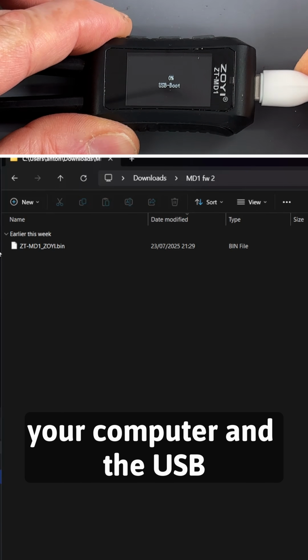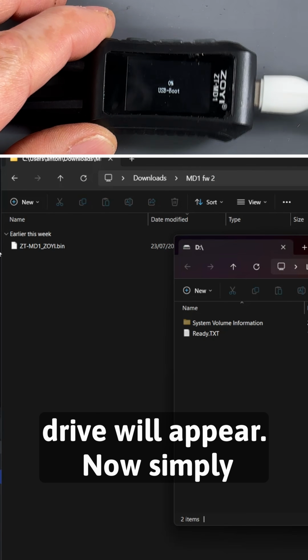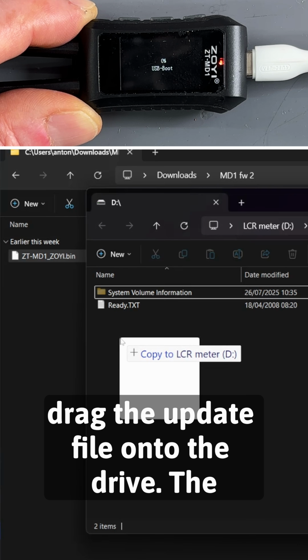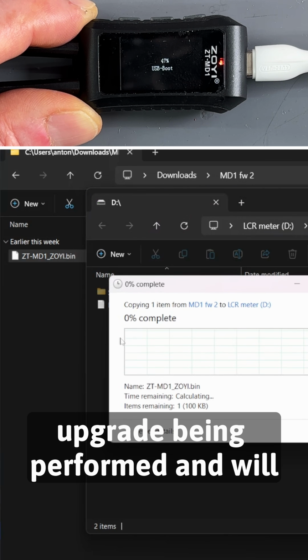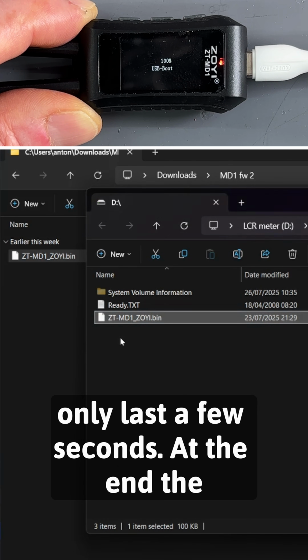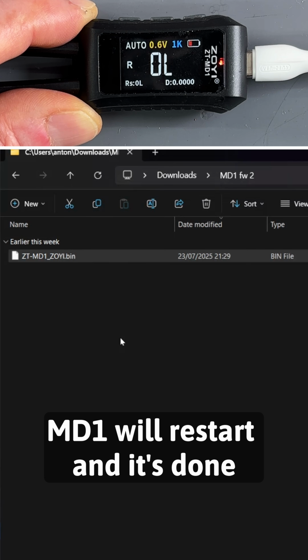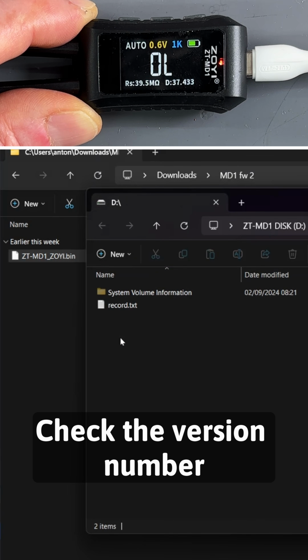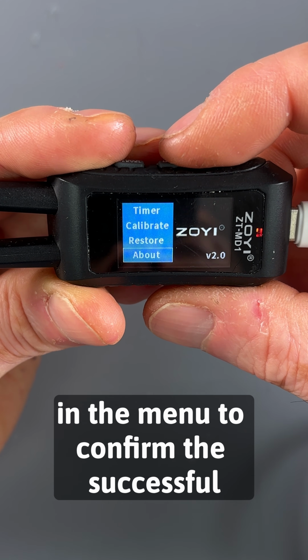Now plug the meter into your computer and a USB drive will appear. Now simply drag the update file onto the drive. The display will show the upgrade being performed and will only last a few seconds. At the end, the MD1 will restart and it's done. Check the version number in the menu to confirm the successful upgrade.